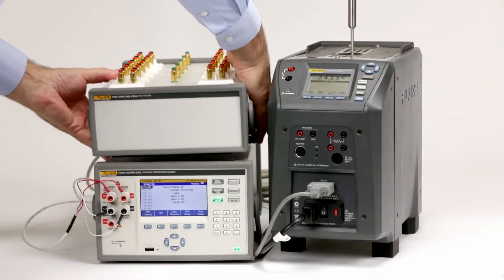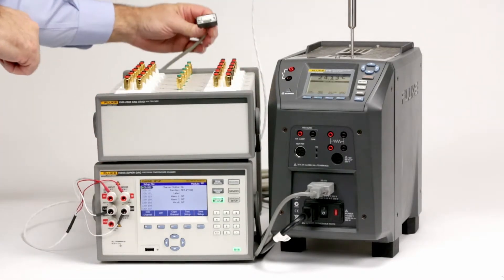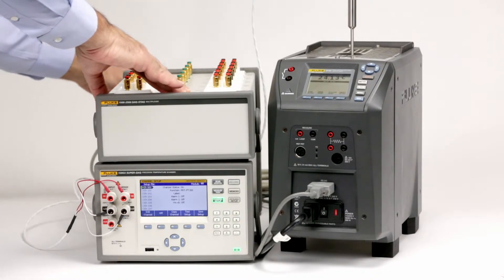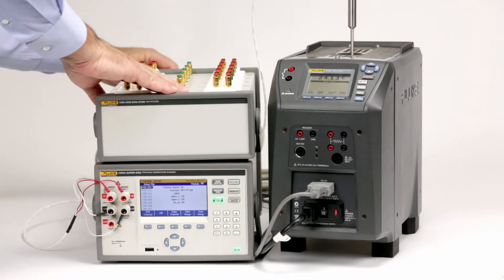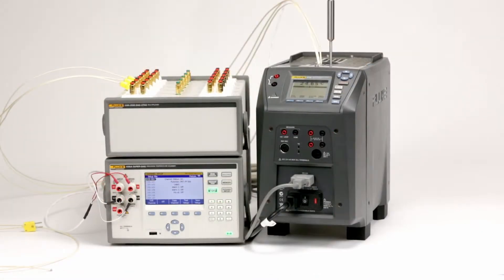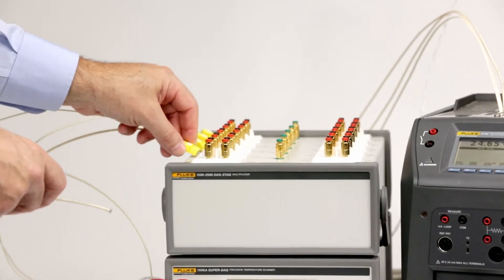Connect the DAQ-STAQ using the two included cables to the 1586. Connect the thermocouples to input connectors on the DAQ-STAQ and insert them into the dry well.